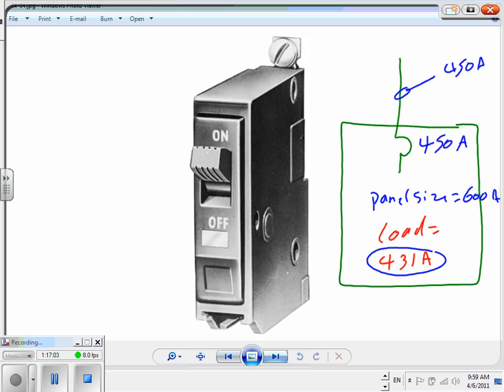Any question, guys? See how you have the size of the panel, the size of the overcurrent protection device, and the size of the cable. The panel and the overcurrent protection device do not have to be the same size. Here's my question for you guys: can I put an 800 amp circuit breaker on a 600 amp panel? No. The overcurrent protection device must be equal or less than the panel rating. Why? Because if you put an 800 amp circuit breaker on a 600 amp panel, you're going to burn that panel. You're going to overload this panel. But I can put less. What did we go to? 450.